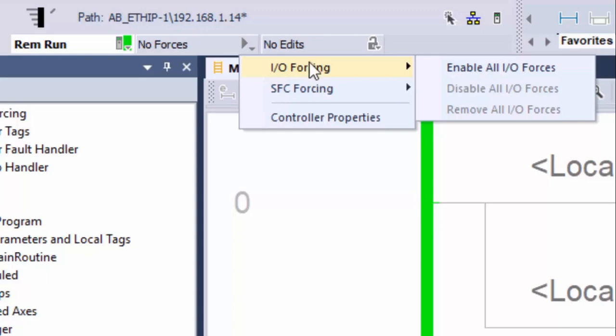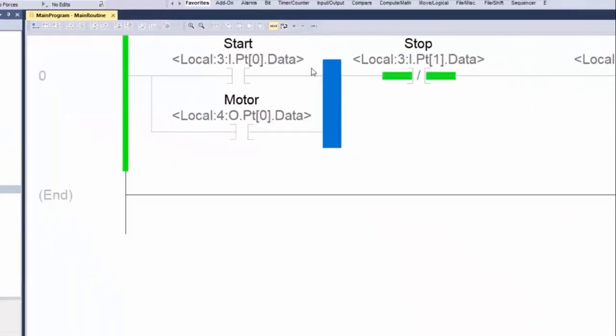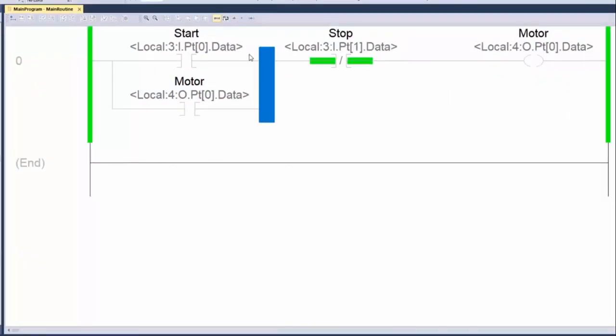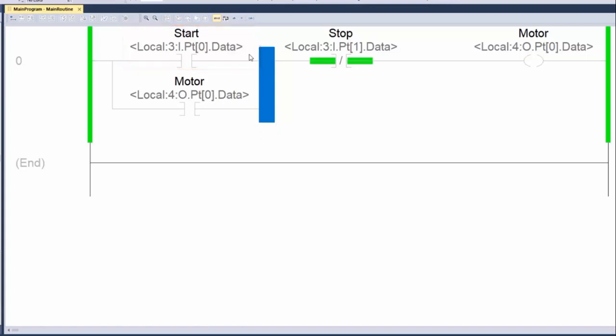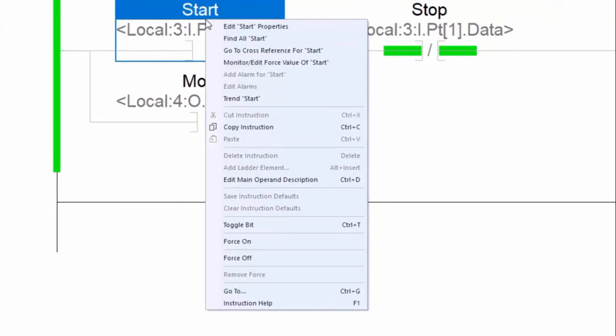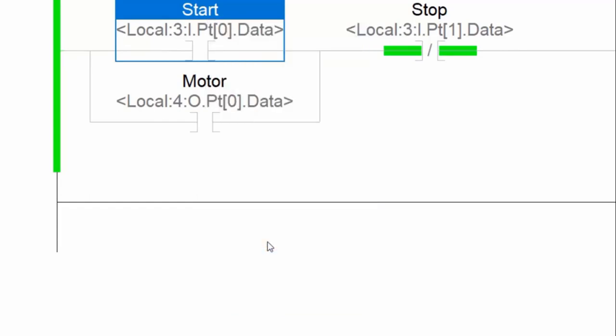We are going to work now on this self-holding logic to demonstrate the forcing feature. Let's start by forcing to 1 the Start Boolean tag, which is alias to a digital input. Right-clicking on the tag, Logic Designer offers the chance to force on or off. To force this tag to 1, we choose force on. The force is now set.